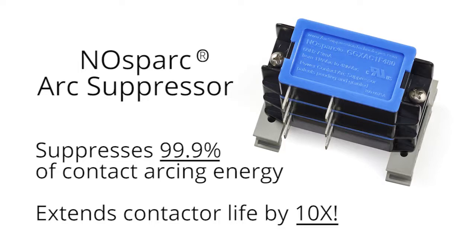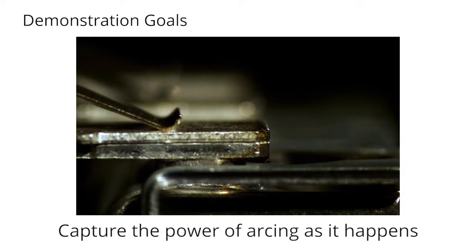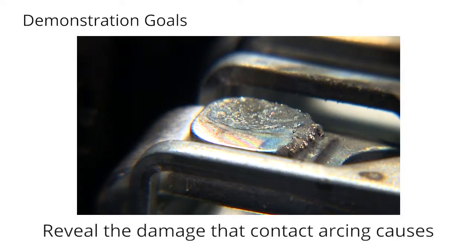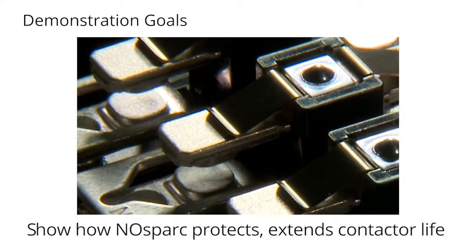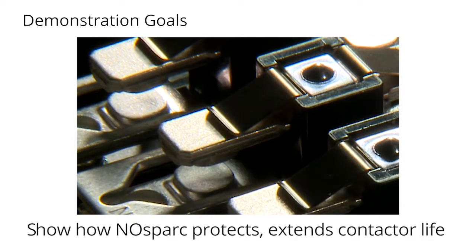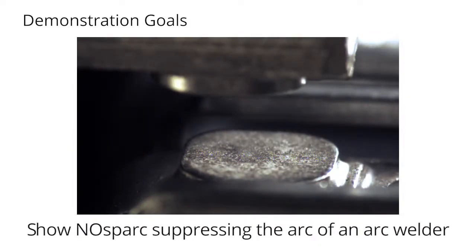This demonstration had four primary goals: use high-speed video to capture the power of contact arcing as it happens; reveal the damage that contact arcing causes; show how NOsparc arc suppressors protect contact points and greatly extend the lives of power contactors; and show how NOsparc arc suppressors can suppress the arcing generated by an arc welder. We chose an arc welder because its inductive load is similar to the load profiles of many motors and compressors.